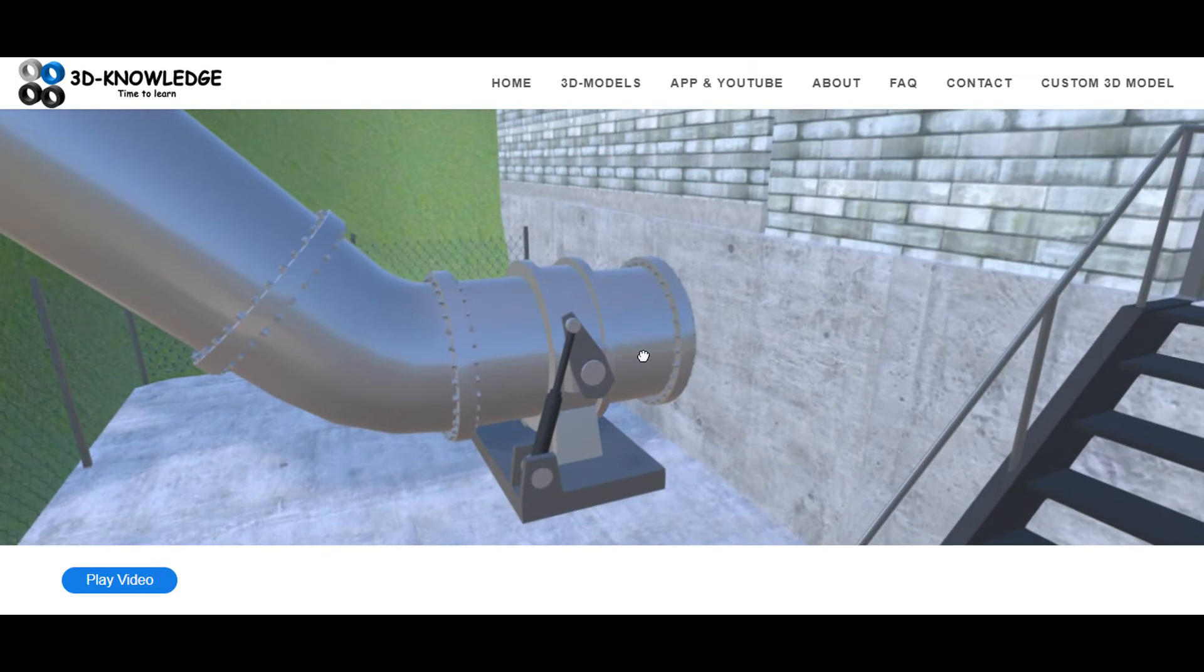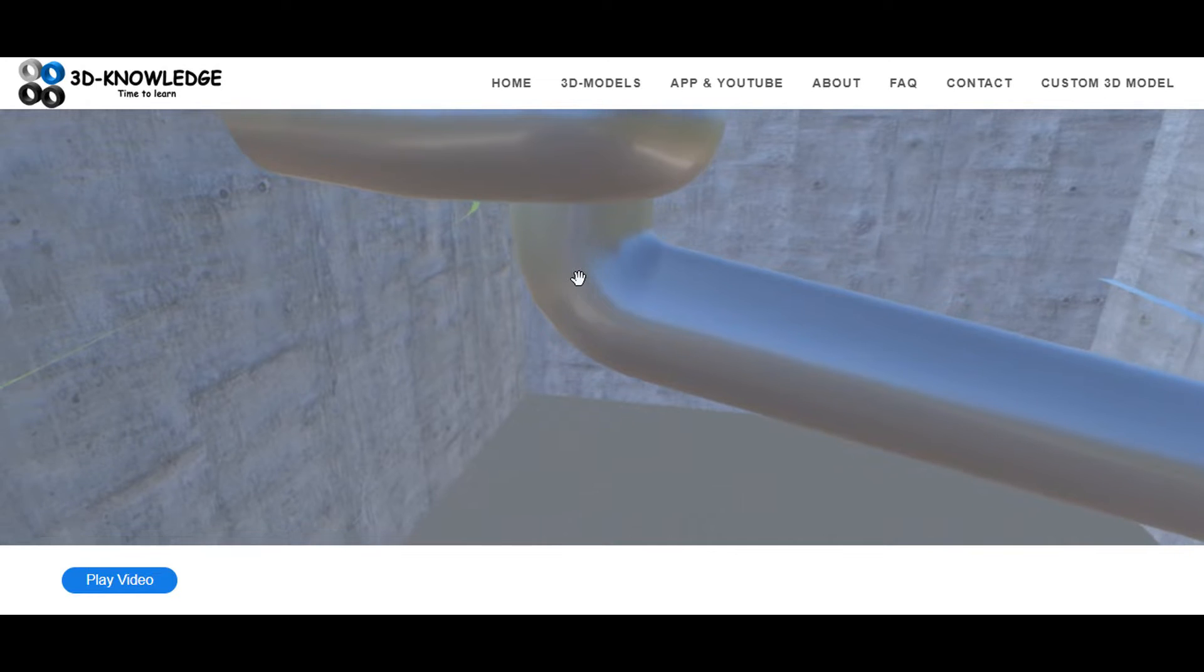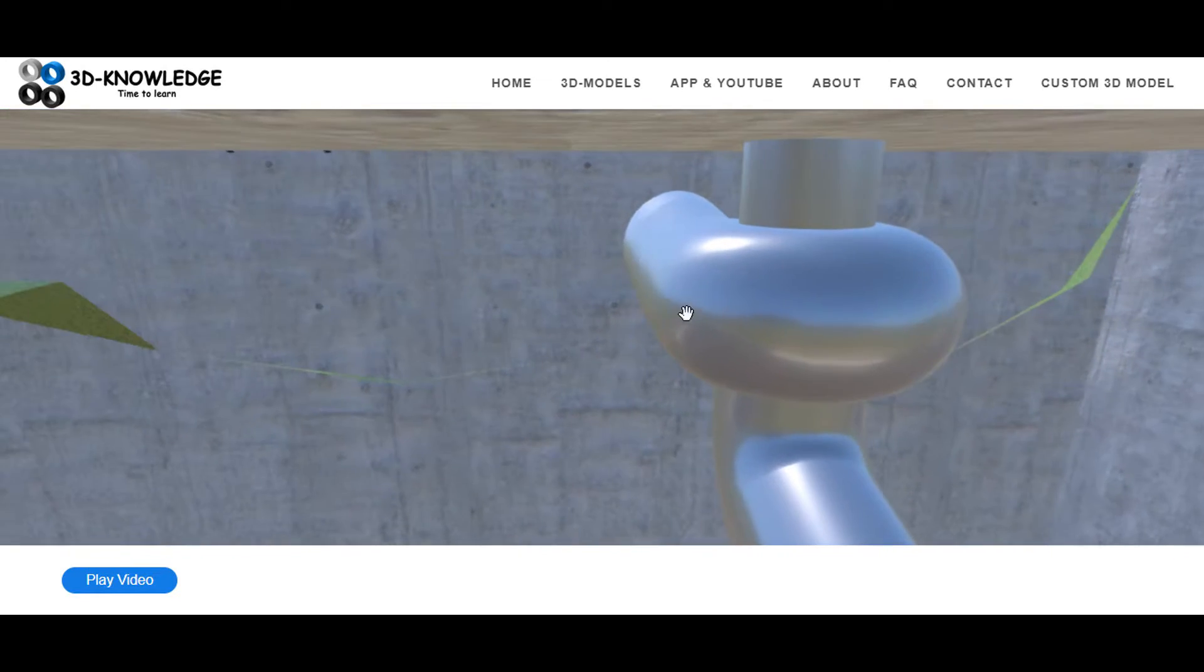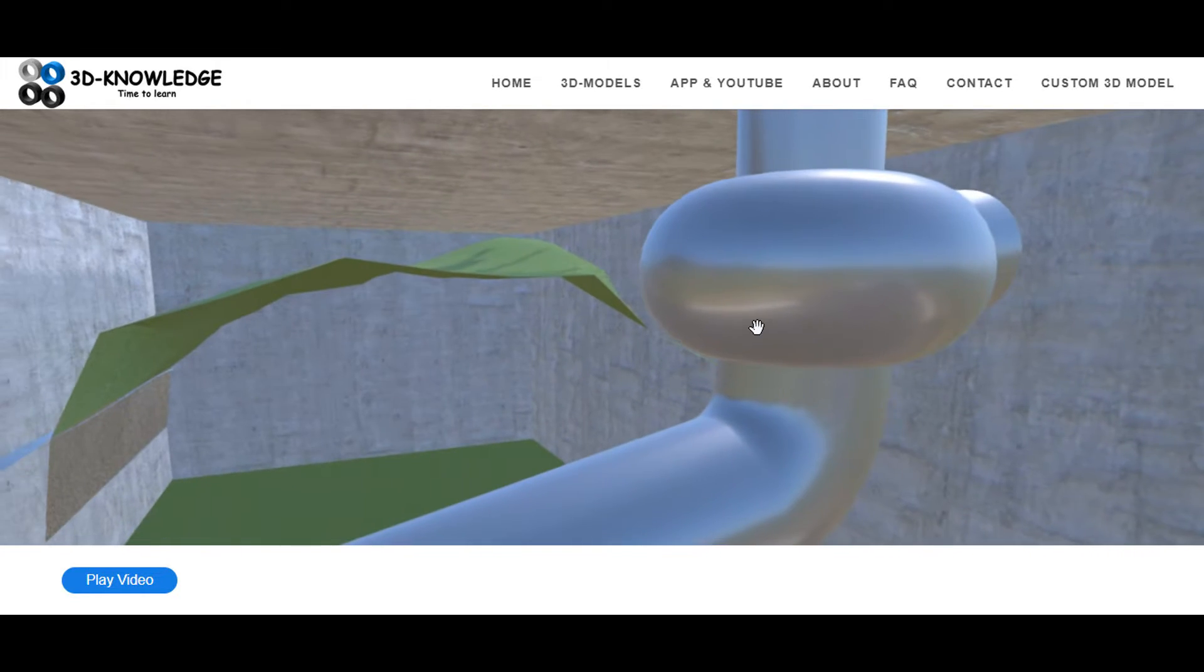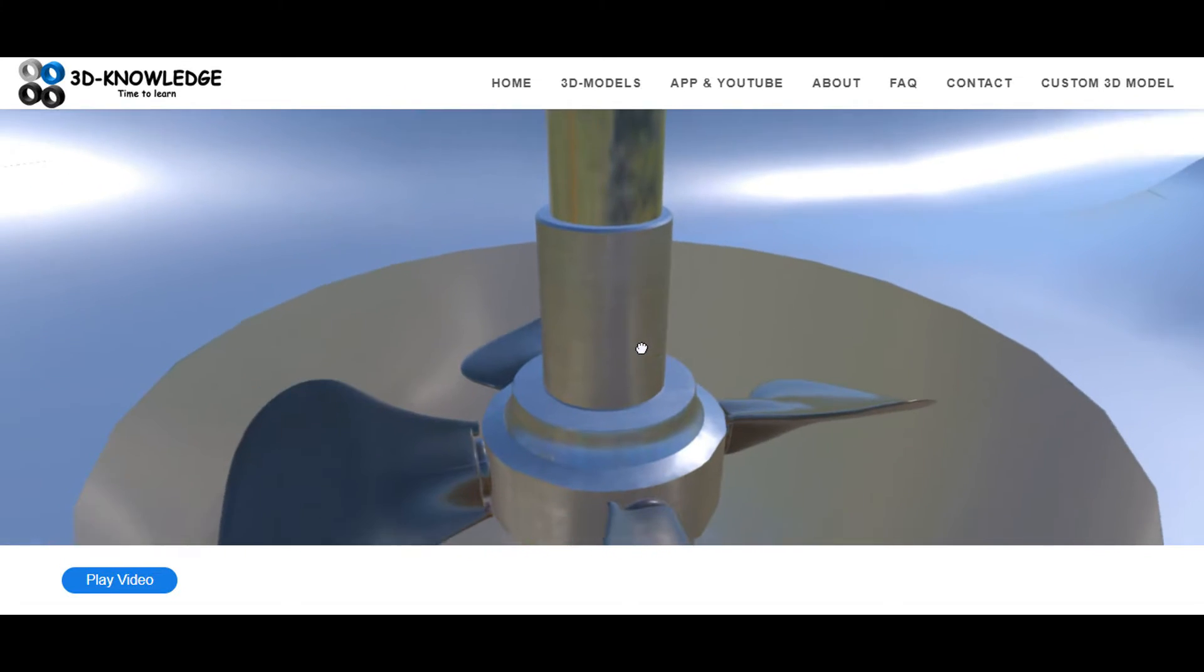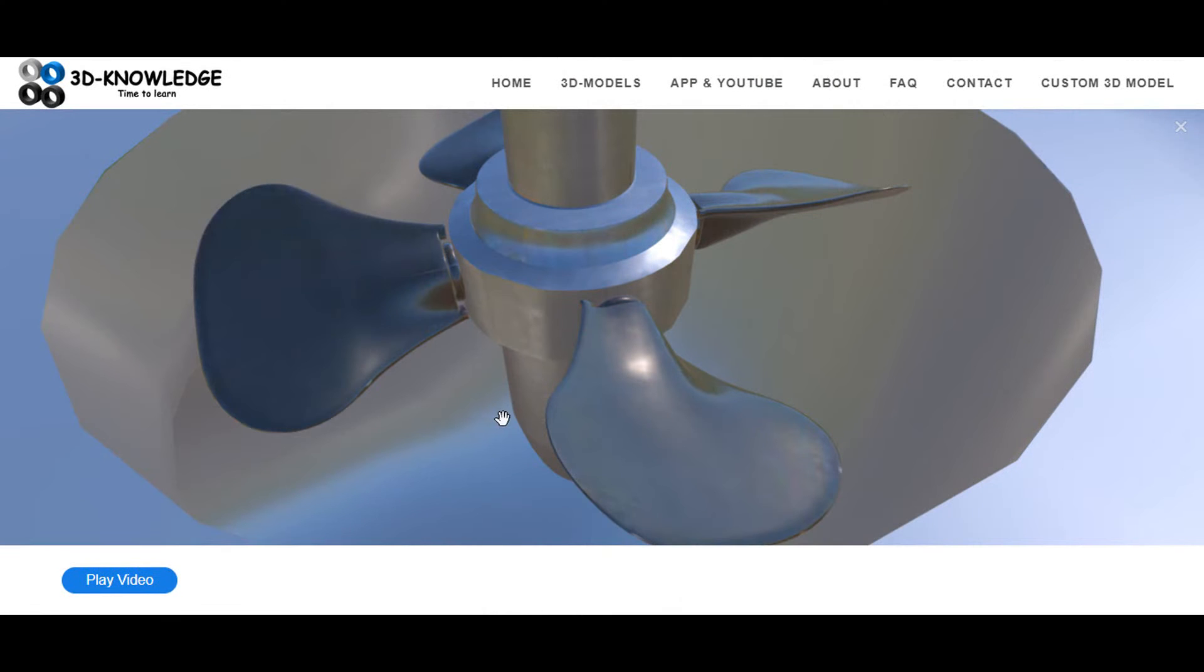So let's go inside now. Okay, so we're underneath the power station. Inside this casing here is a Kaplan turbine, it's a vertically orientated Kaplan turbine, so the water comes in, flows in through here and into the casing. In the casing itself, there's the vertically orientated Kaplan turbine. There will normally be inside here some sort of wicket gate which will allow you to divert water to the Kaplan turbine. A Kaplan turbine is more or less like a ship's propeller and here you can see it's vertically orientated, it's pointing straight down.